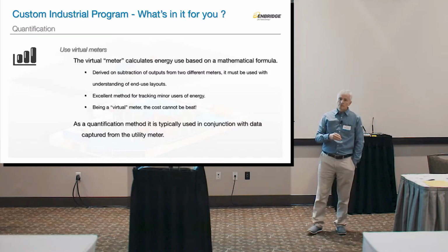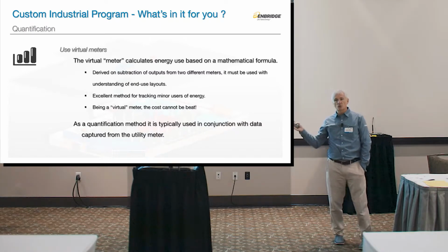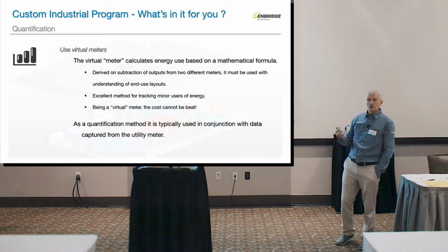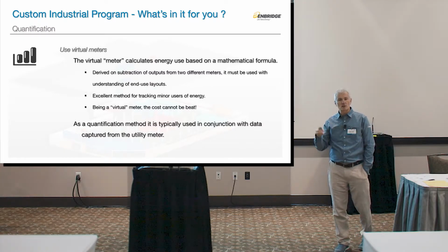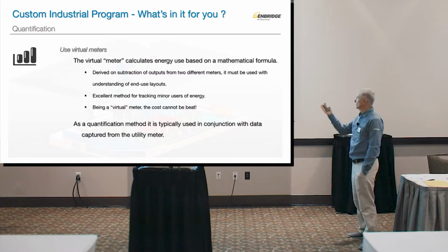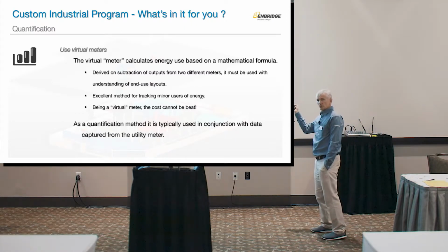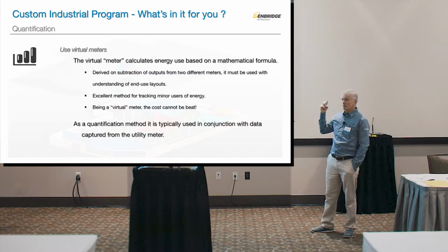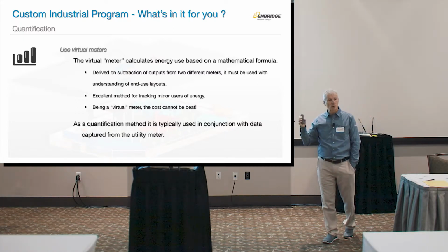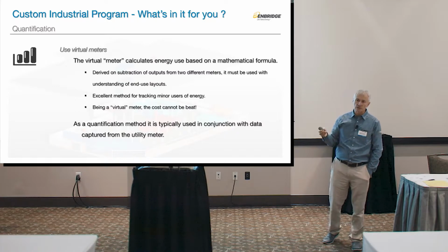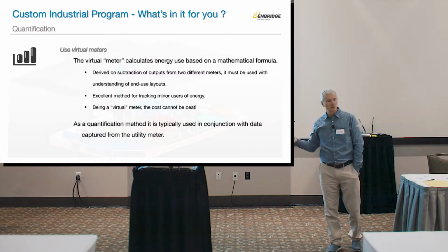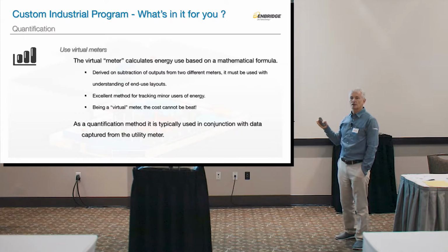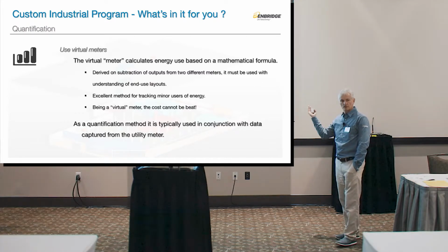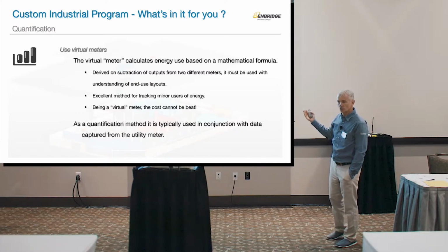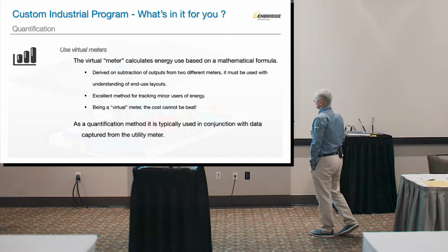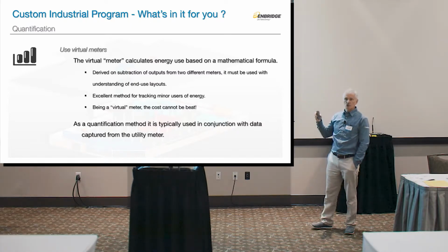The other method, as pointed out, is virtual meters. This essentially calculates energy use based on two other meters you already have, subtracting the values to give you an idea of how much you use. We recommend this methodology for minor users—if they're not really important in a typical manufacturing facility, your unit heaters would be ideal for this, because they use such a minute amount of energy that even if you're off by 50%, you'll still only make a 1% error on your total project. So the virtual meter is the cheapest of all.